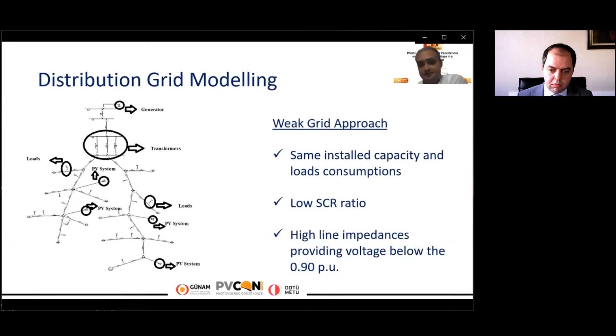In our strong grid approach, the layout is the same as the weak grid, and we have 4 megawatt installed capacity, and we have 20 loads having consumptions changing by minutes. In the strong grid, we have very low line impedances, providing 1 per unit for each substation bus. When we come to the weak grid, we have the same installed capacity and the same load consumptions. But since there are high line impedances, we have a very low short circuit ratio and very low short circuit power and currents also. We can see the voltage level below 0.9 per unit.